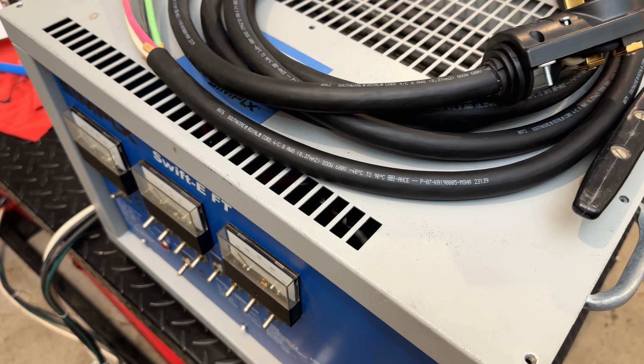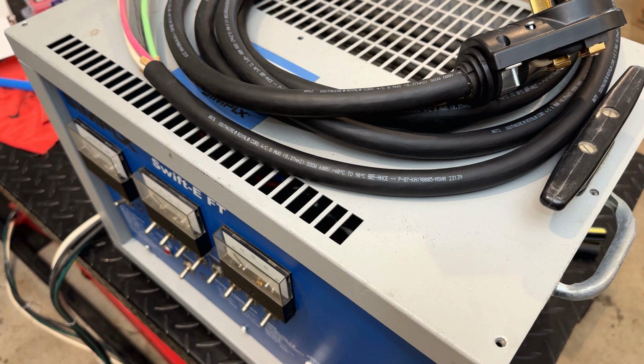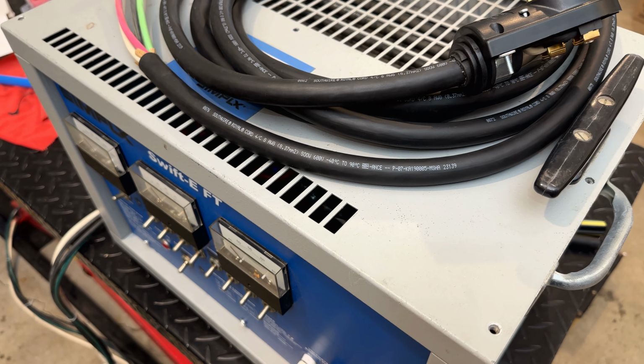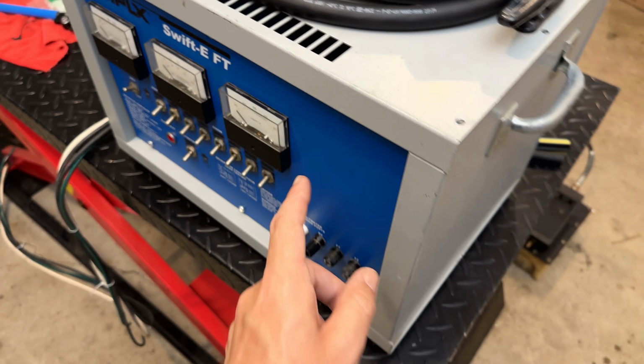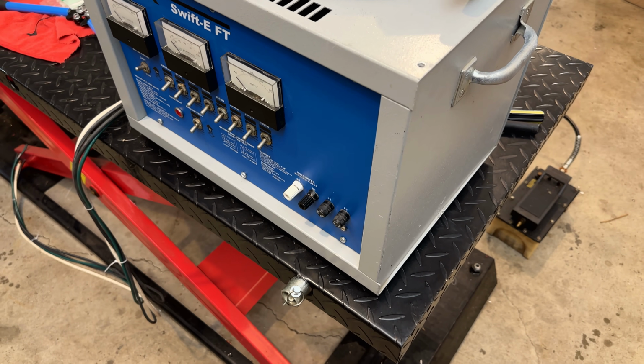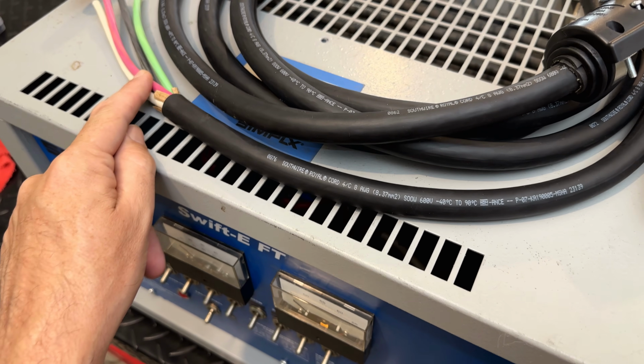There's nothing wrong with using 6, that's good up until about 55 amps. In this case, we're only pulling 10,000 watts, which is 41.6 amps, and for something like that, 8 gauge wire should be fine.